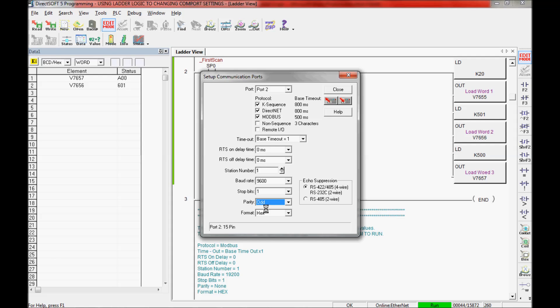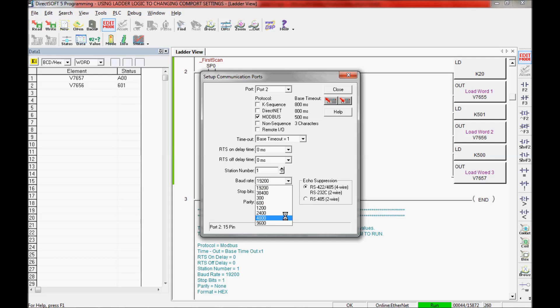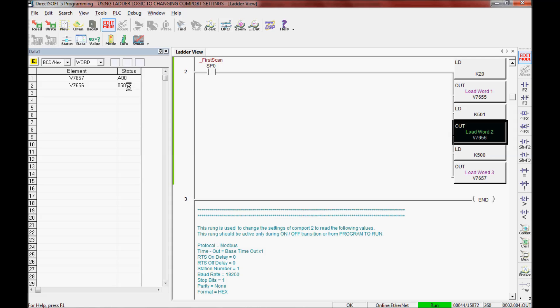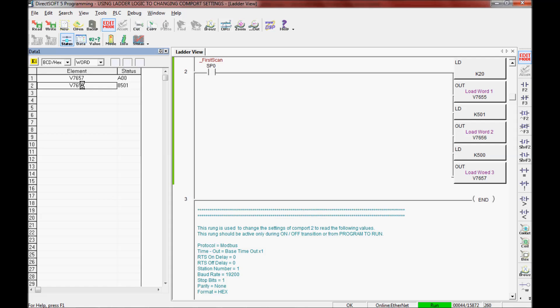The settings I had before should still be in the processor since I haven't downloaded them. I'm going to click this button to upload the values from the processor and place them in the screen. As you can see, all the settings went back to where I originally had them. I'm going to change them back again because I want to start with the default settings, then load that to the processor by clicking the Load button. Now I'll click Upload — as you can see everything has been changed. I'm going to click Close. Right now I have a value of 8501 in my V-memory location for word number 2.